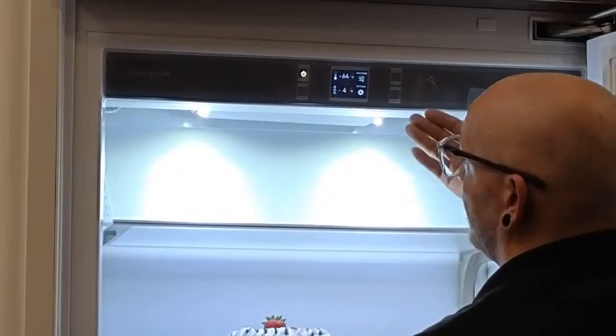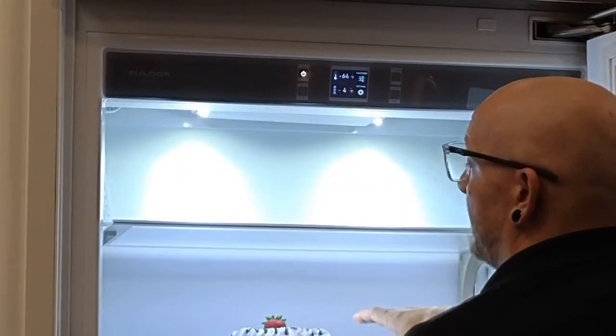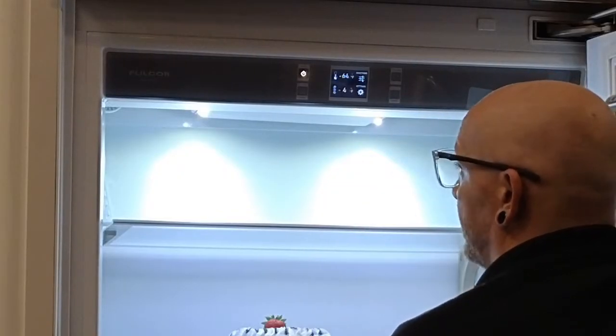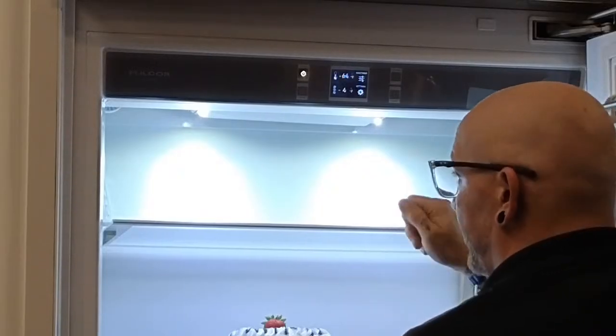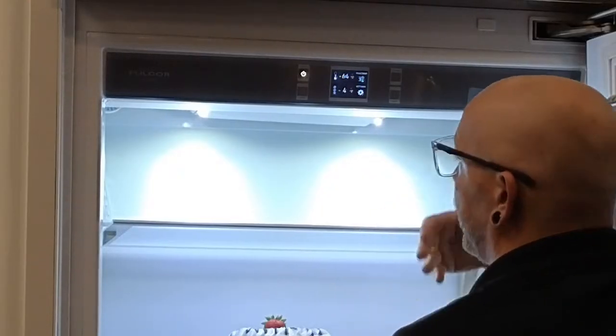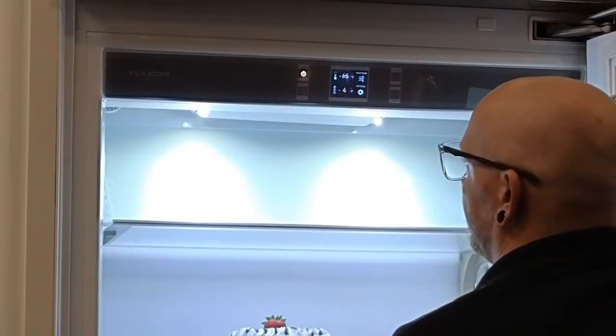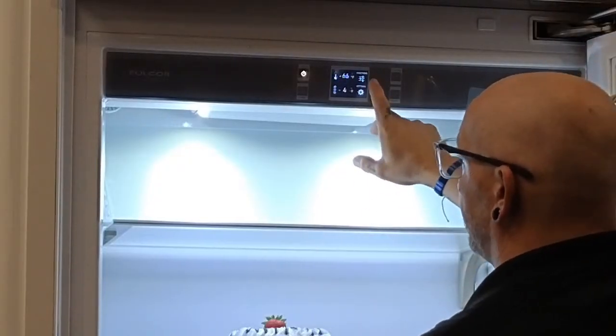Because oftentimes, if you have no ice and no errors, the machines may have just lost communication, and a simple hard reset, shutting off the breaker, turning on the breaker, will regain communication between the two. All right, so those were functions.